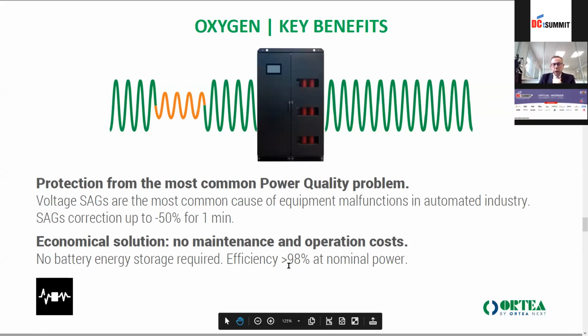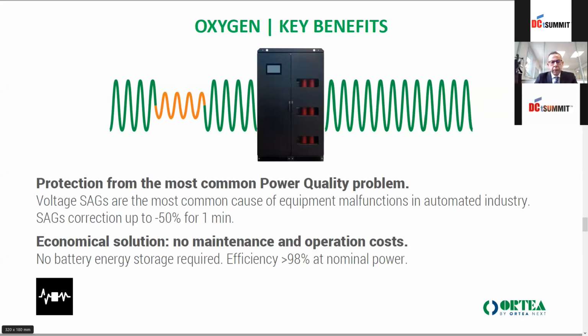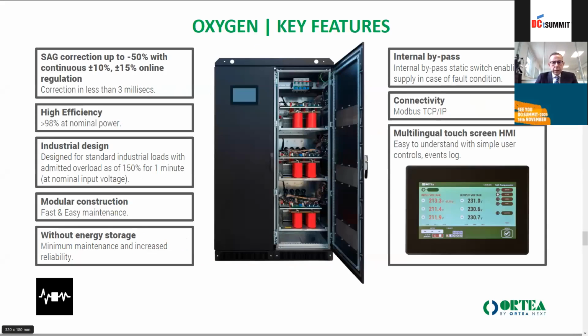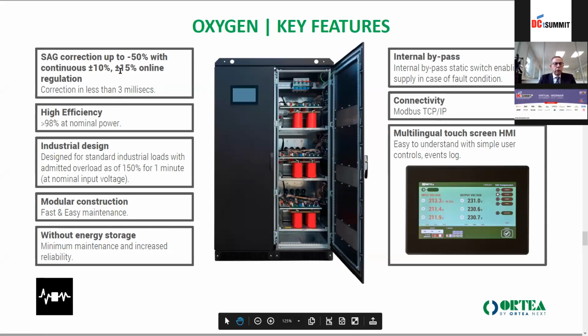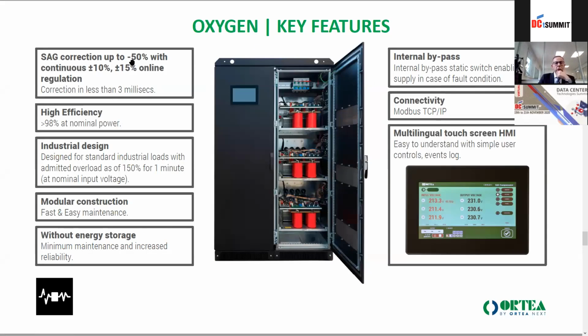So having an efficiency which is over 98%, you will have always your feeding of a line with very high quality of voltage level. The unit can be plus minus 10% or plus minus 15% as a standard, but can reach also minus 40 or minus 50% as a SAG. It's always a modular system, as you can see, with different additional components that we can add to the unit, like bypass system or interrupting devices, etc.